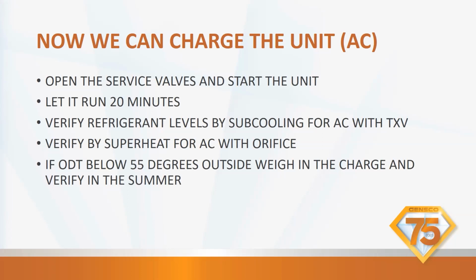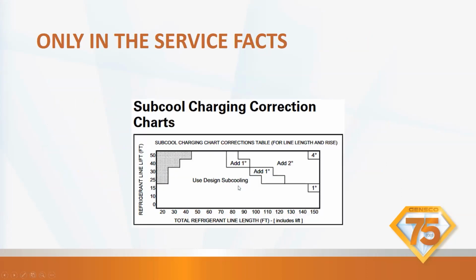What I always did was I would weigh in my charge and then I would just bump the contactor just to make sure my electrical was right and that it is going to run. Just enough to hear the compressor kind of try to start, and then I would shut it off. I never ran it when it was really cold because I don't want to break the compressor. So this is how we charge for air conditioning mode.